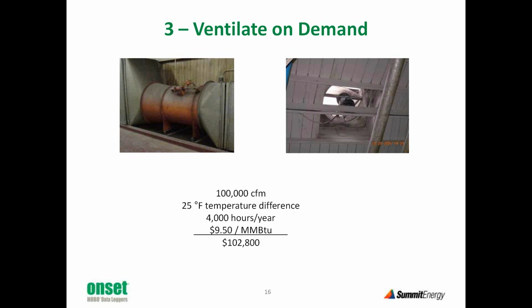I just put one example here. If you bring in 100,000 CFM from outside, and it's 25 degrees colder outside than it is inside, if you do that all winter, and you're paying $9.50 a million BTUs for gas, that's 102,000 bucks, almost 103,000. So, as I said in the beginning of this discussion of number 3, this is a huge opportunity for many facilities. Now, my example is given for heating, but the exact same thing applies for cooling.